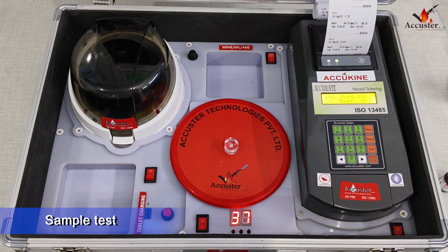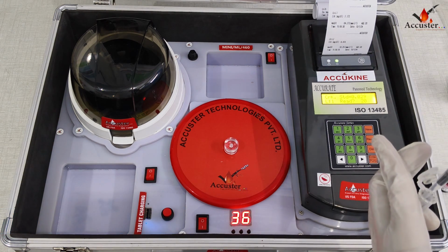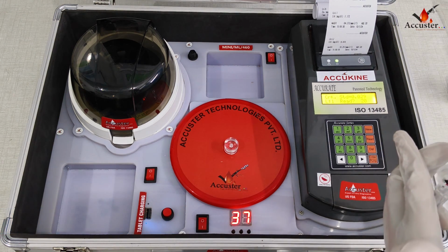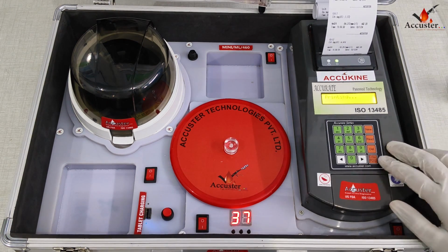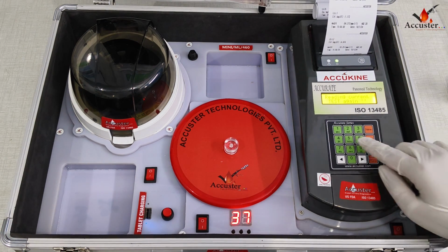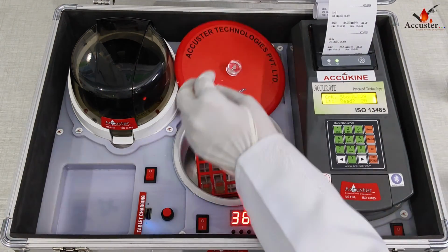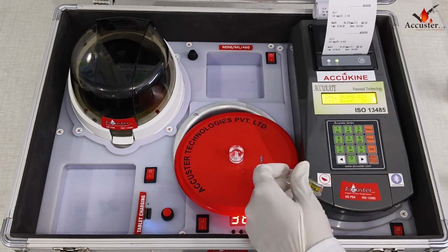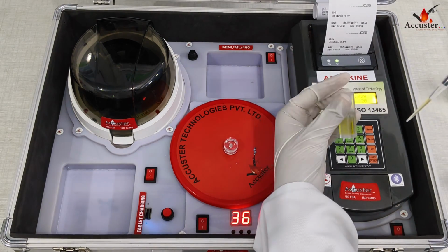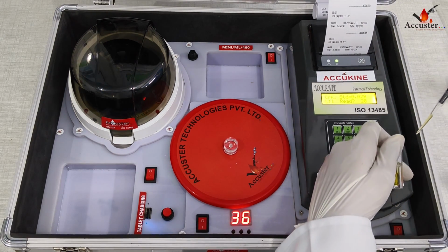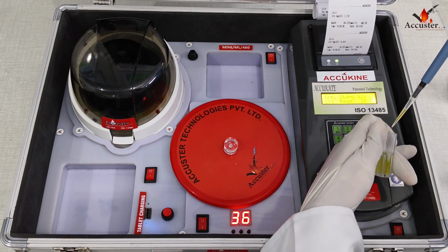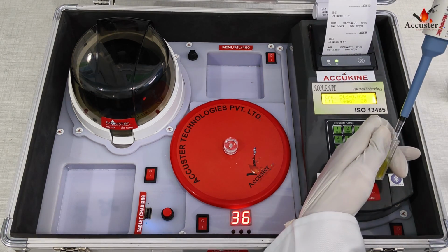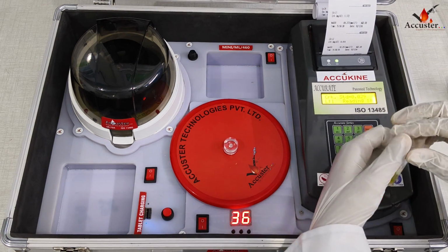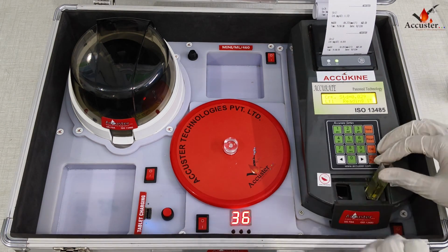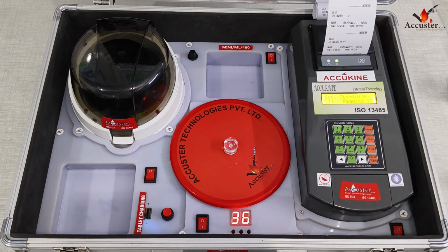Now we will perform tests for patient samples. We have samples from two patients labeled as label 1 and label 2. To begin, press enter and then press 1 to assign a label ID for the first patient. Next, take the cuvettes from the incubator and mix 50 microliters of the patient serum and press enter while mixing. Then insert the cuvettes into the analyzer. The reading will take 80 seconds to display.